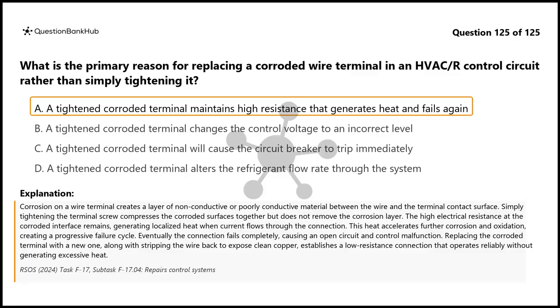This heat accelerates further corrosion and oxidation, creating a progressive failure cycle. Eventually the connection fails completely, causing an open circuit and control malfunction. Replacing the corroded terminal with a new one, along with stripping the wire back to expose clean copper, establishes a low-resistance connection that operates reliably without generating excessive heat.